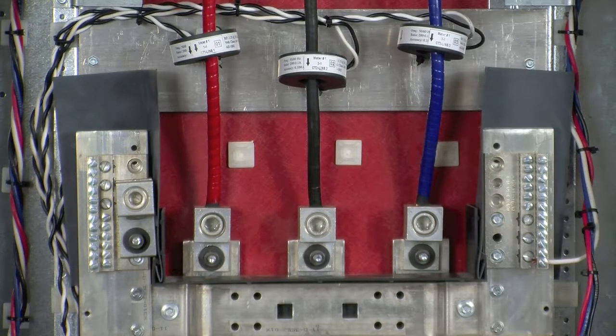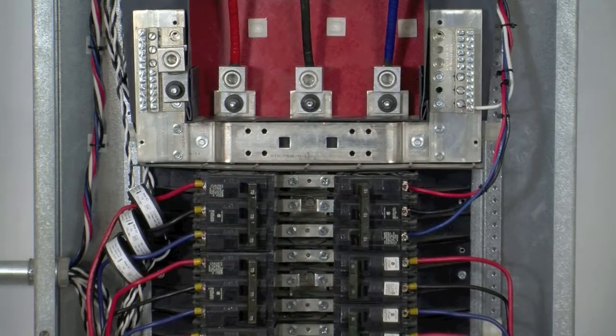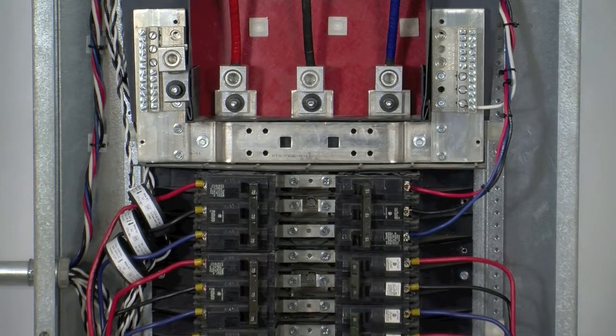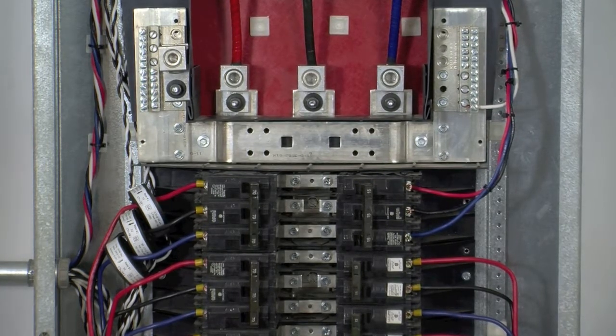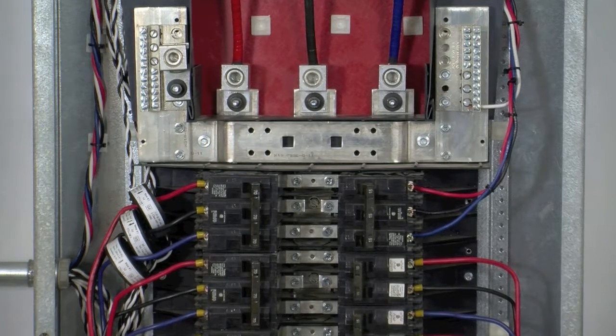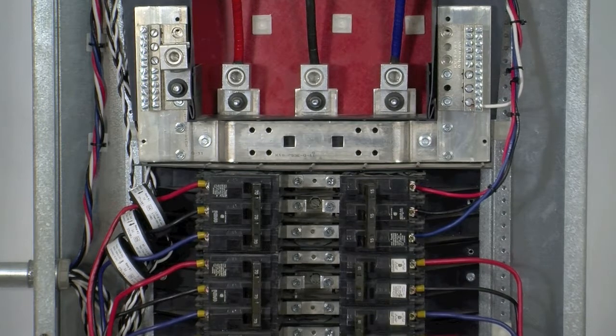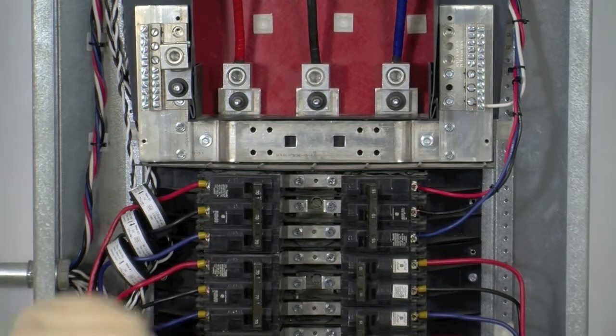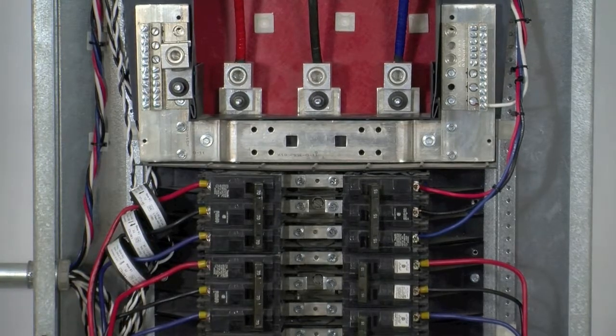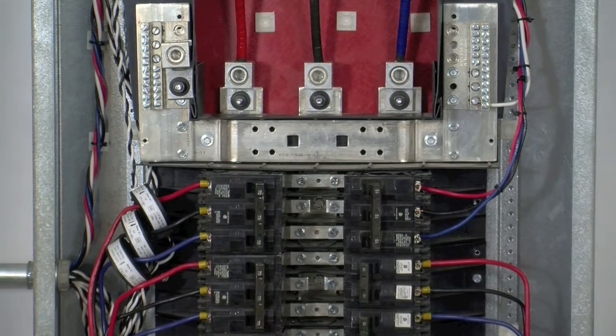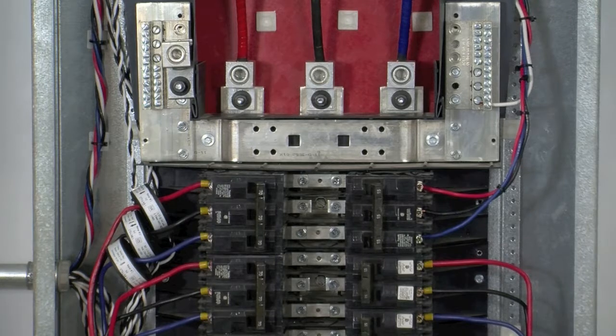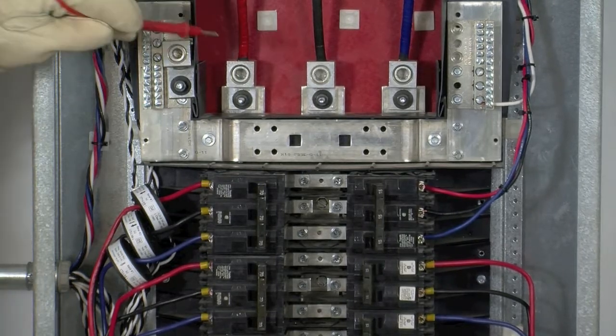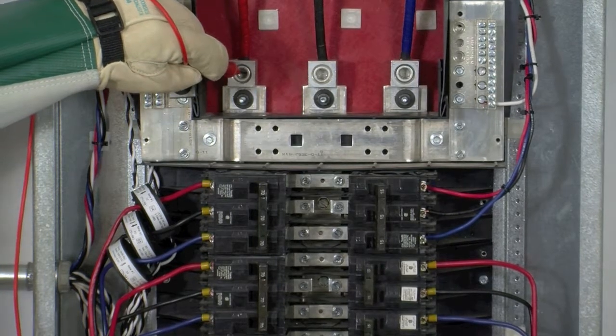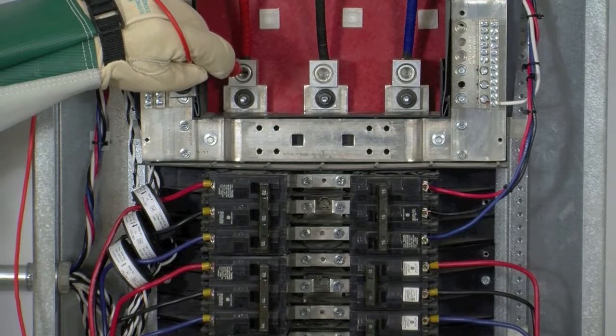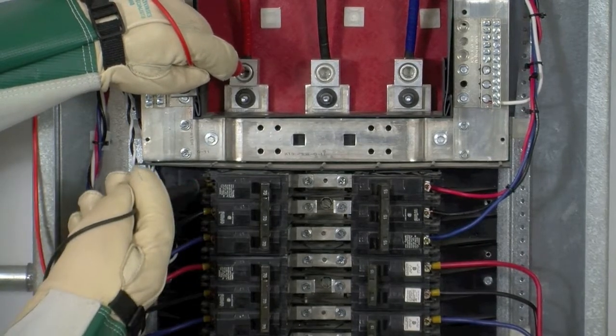Now let's move on to the CTs for meter 2. Because we are installing CTs on a breaker load, a phase test is required to ensure that each CT is being installed on its correct phase. In order to perform this test, we need to energize the panel and temporarily turn the breaker to its on position. We're going to take a multimeter and set it to check for alternating voltage. We're then going to take one of our probes and place it on phase A or line 1 main feed. Take our other probe and place it on what we believe to be phase A on the breaker.